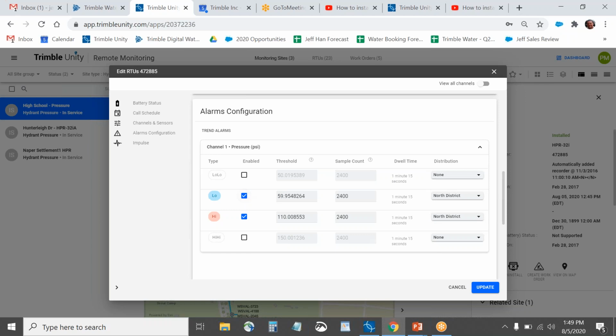You can also set a low alarm—say if the PSI ever drops below 35, I want a specific person to get an email or text message. You can also select multiple groups, like North District and that person together. It's very easy to set who the distribution group is, so you can set low alarms, high alarms, or both, and control who gets notified.